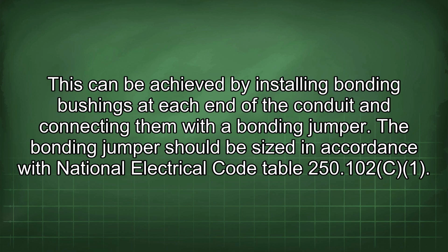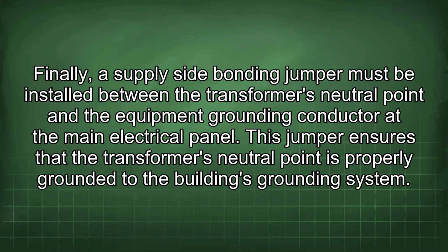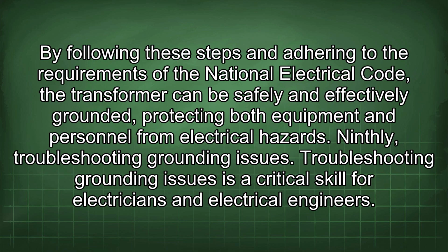250.102. Finally, a supply-side bonding jumper must be installed between the transformer's neutral point and the equipment grounding conductor at the main electrical panel. This jumper ensures that the transformer's neutral point is properly grounded to the building's grounding system. By following these steps and adhering to the requirements of the National Electrical Code, the transformer can be safely and effectively grounded, protecting both equipment and personnel from electrical hazards.